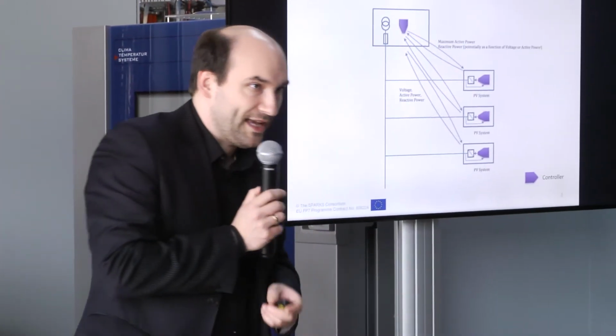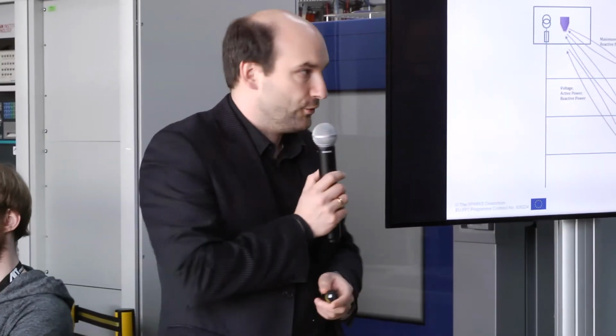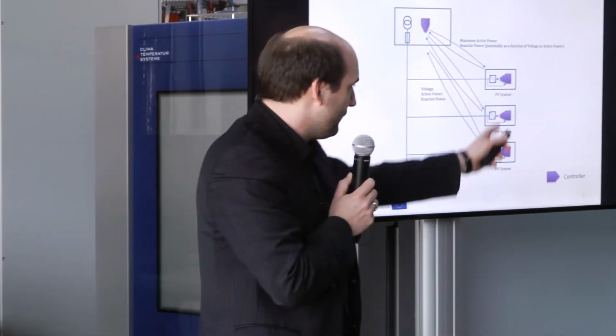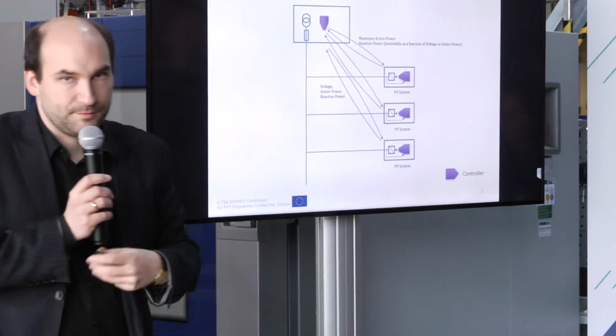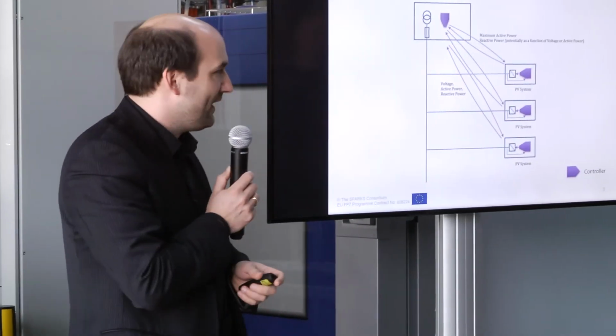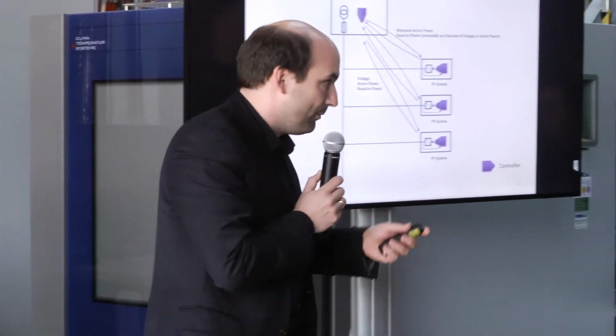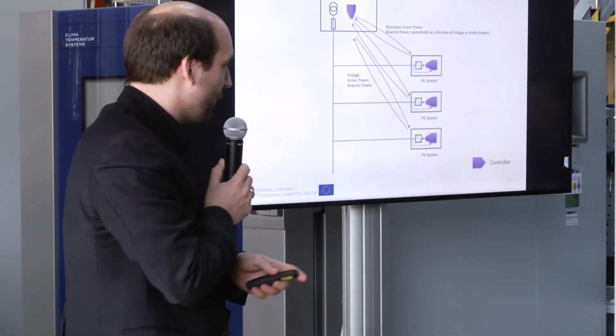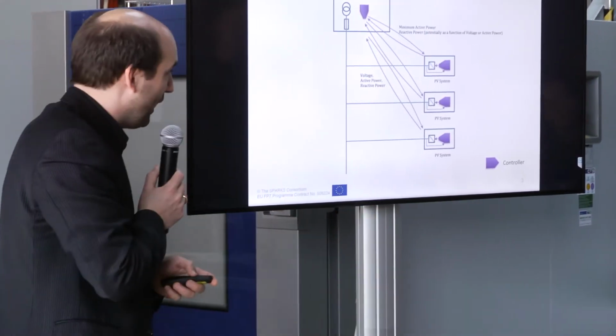In this system, as Henrik pointed out before, we have to take care of the voltage. When the PV systems feed power into the grid, the voltage rises. In order to maximize the potential of infeed, we control the voltage using reactive power management.